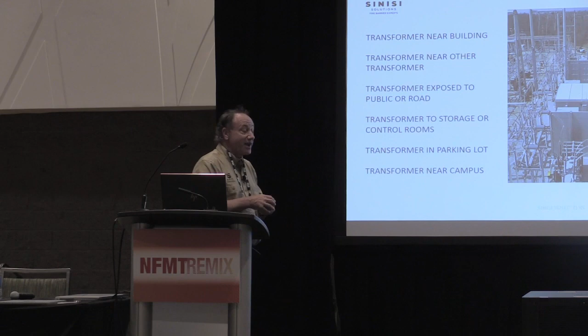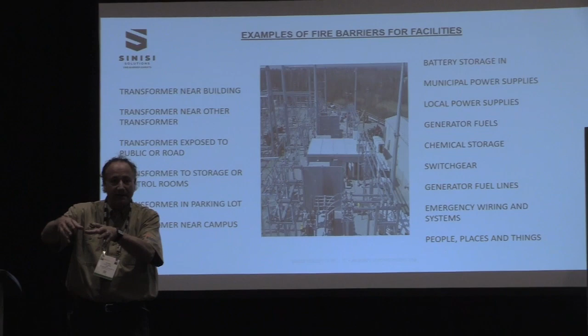We also protect generator fuel storage and local power supply. We have clients in the steel industry with substations right on their plant or job site, as well as fuel lines for generators. I mentioned this to a couple people at a show and it turned heads, because now everyone puts generators on the roof so they don't flood out in the basement, but they still need to put the fuel somewhere. So they put it in an underground fuel tank and pump it to the roof. How do you get fuel from the basement to the top of a 30-story building? Through a fire-rated shaft, again using fire barriers and protection.